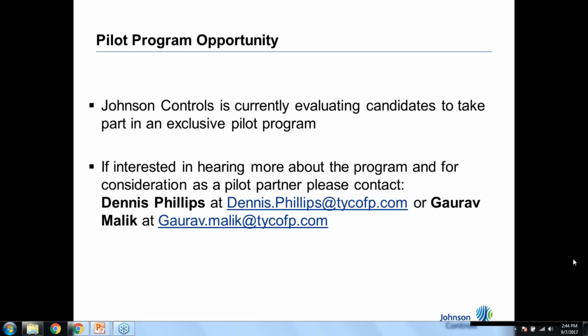Sure. So, again, like Dennis also mentioned, this is a performance-based design. And with the testing we've conducted at UL, we've conducted 12 full-scale fire tests. The application we're targeting today is 35-foot ceiling heights, 30 feet of storage with exposed expanded plastics. If it's anything outside of that, we'd like to have that discussion with you. It is possible, depending on what that application is, that we may be able to support it. But again, we'd like to have that conversation with you. We'd like to understand what commodities you'd like to protect, what the challenges and hazards are you're looking at, and we can work on that together.